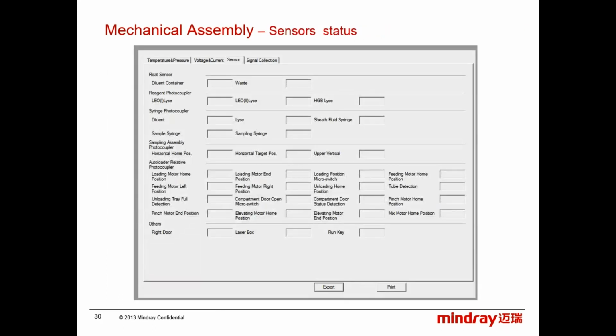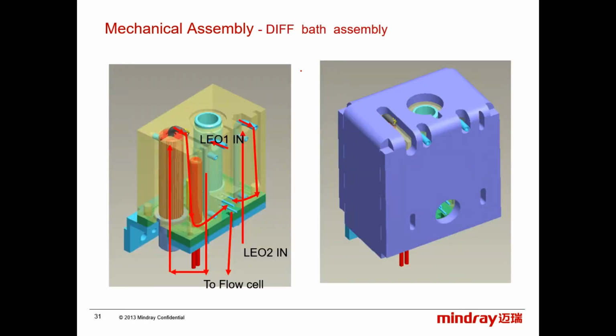This is the sensor status from the software. You can actually see all the sensors from the software. This is the diff bath assembly. It does not need any maintenance. If there is some problem related to the temperature or leakage or any related problem, you need to replace it directly. This is not a modular design. You just replace it directly. There is no maintenance inside.